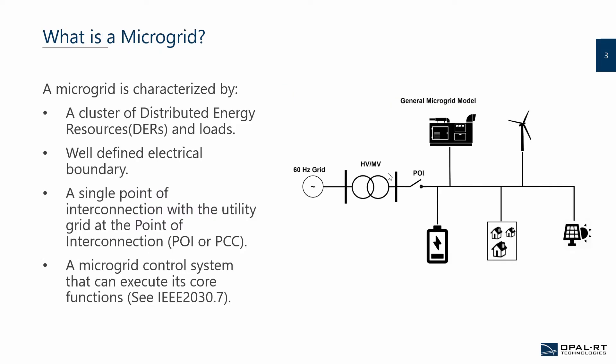First I will give a brief definition to what is a microgrid. I assume it's a topic that most of our audience is already familiar with. However, a microgrid is essentially a portion of the electrical grid that is capable of islanding itself on its own and run autonomously, and that is aided by a dedicated microgrid control system of which functional requirements can be found in the standard IEEE 2030.7. A microgrid has a dedicated point of interconnection with the electrical grid and has its own set of resources and loads that are mostly controllable, so that a microgrid can be allowed to control the power flow through the point of interconnection, island itself, reconnect back to the power grid, and so on.